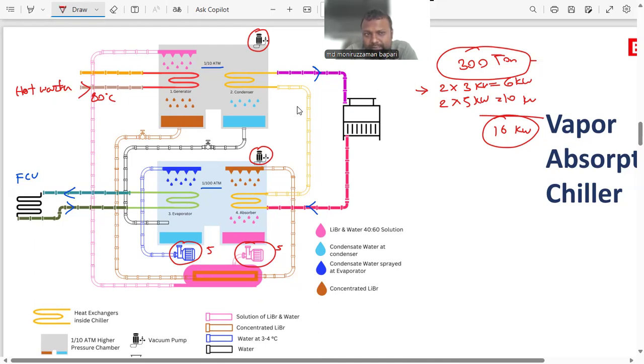However, if you have this vapor absorption chiller, it is very, very efficient. It can bring the electrical bill down to very low. Just see here, 16 kilowatt is running a 300-ton chiller only. If you have waste heat, and if you get freely 80 degrees centigrade hot water, life is beautiful, isn't it? You can run the whole chiller with a very low electrical bill. So it will be very low operational cost, low cost of production, higher profit margin, business runs well. Usually vapor absorption chillers are mostly used in factories and industries.